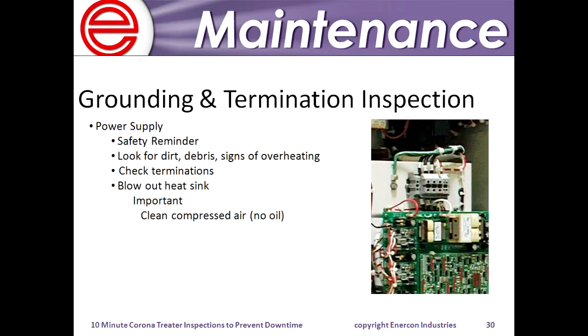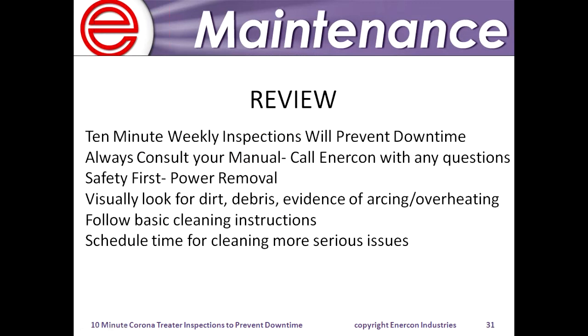And then this is inside the power supply. A real quick thing that we want to do is, with all the power removed, especially upstream of the power supply, just open it up, look for any dirt or debris, vacuum it out, blow it out with oil-free compressed air, and look for any signs of burning or overheating. If you do find connections that are burned or overheating, it's likely because that connection has loosened up over time. Then you would want to take corrective measures to re-terminate it, or whatever the case may be, to prevent any further problems down the road.